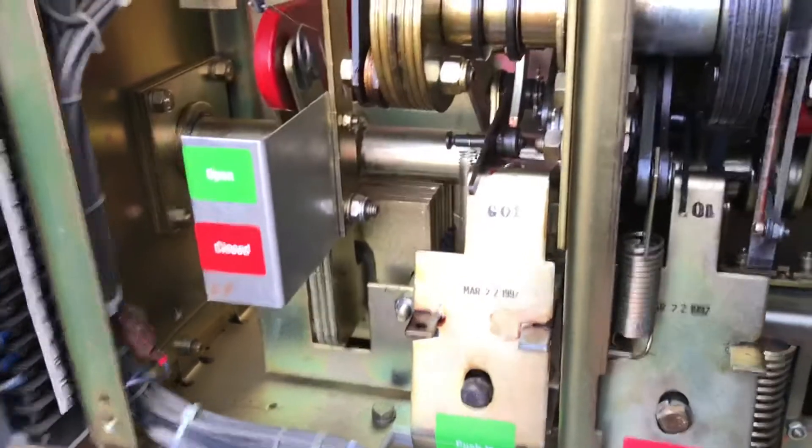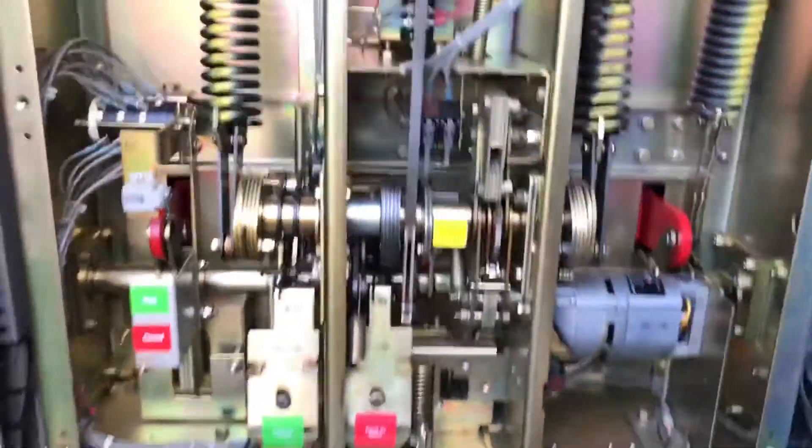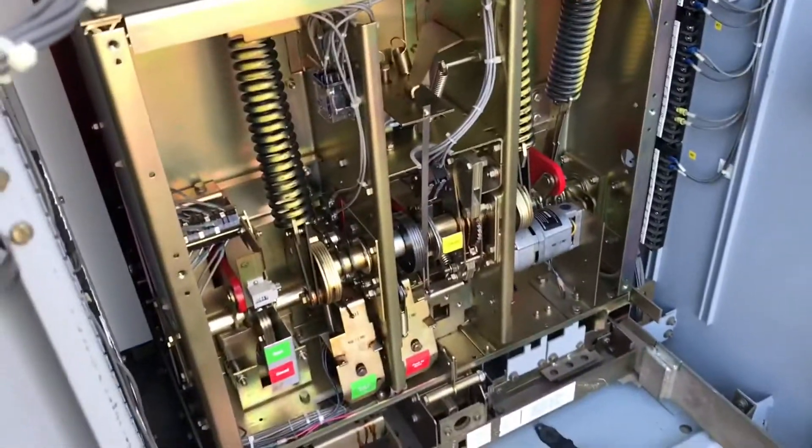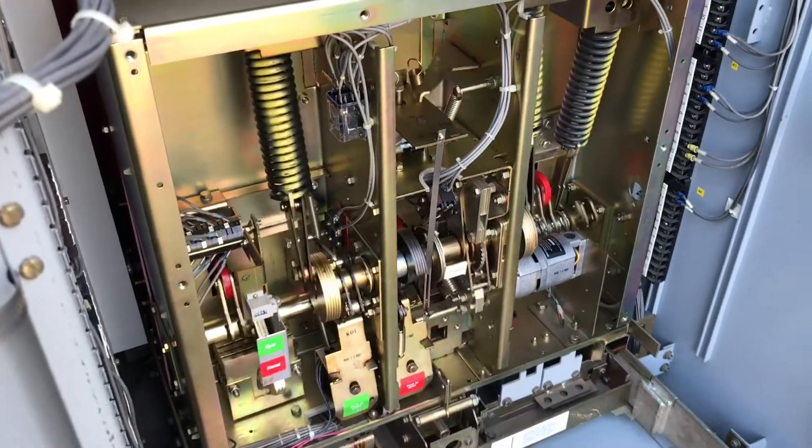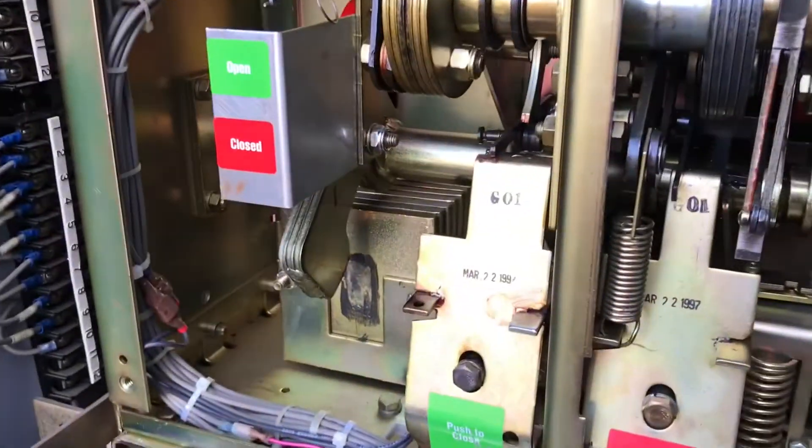And now the breaker is open again. It's fully charged and we'll go through this again. Come back to the control switch on the door, I'm going to turn the switch, breaker is closed again, and the springs are recharged.